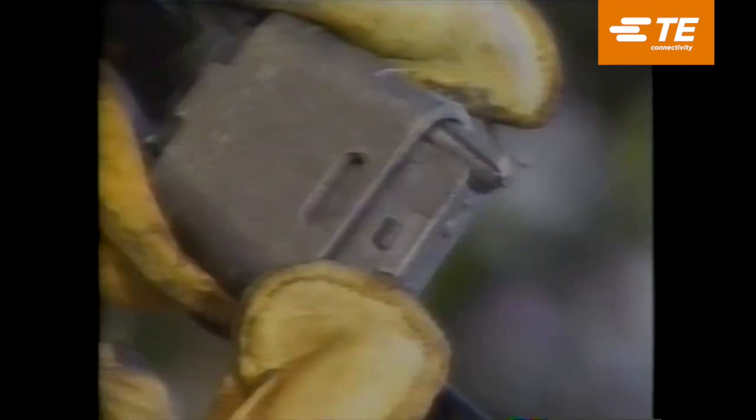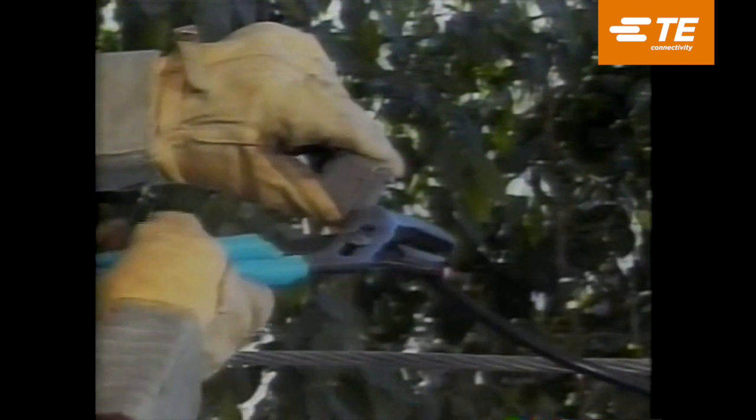Place the wedge into position between the two conductors and push in place with the locking boss facing you. The wedge can be tapped with the pliers to snug it in position. Tapping the wedge firmly between the conductors will reduce the pressure required for final termination.